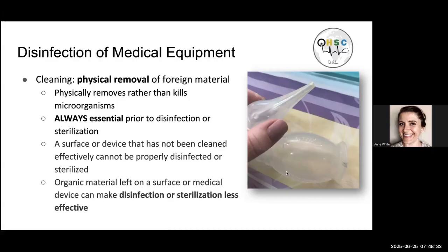In the picture I show here of this suction unit, you can see at the very end of the tip there that there's still a bit of material. That wasn't physically removed. And if there's material like that left on there when it goes forward for disinfection or sterilization, that material can make the disinfection or sterilization process less effective. And so cleaning is the first step. If there's blood or meconium, mucus on the equipment that we're using, the first step is cleaning to physically get rid of any of that foreign material that we can see. Next step, please.